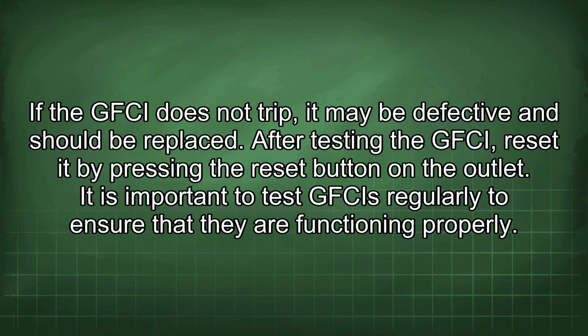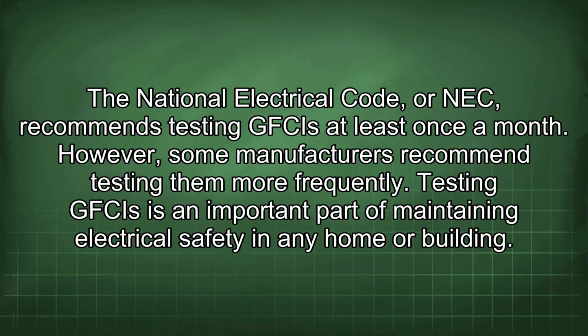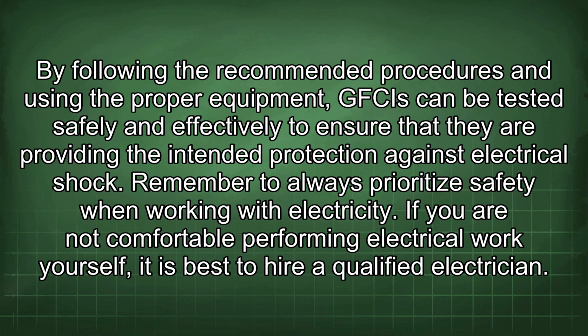It is important to test GFCIs regularly to ensure that they are functioning properly. The National Electrical Code, or NEC, recommends testing GFCIs at least once a month. However, some manufacturers recommend testing them more frequently. Testing GFCIs is an important part of maintaining electrical safety in any home or building. By following the recommended procedures and using the proper equipment, GFCIs can be tested safely and effectively to ensure that they are providing the intended protection against electrical shock.